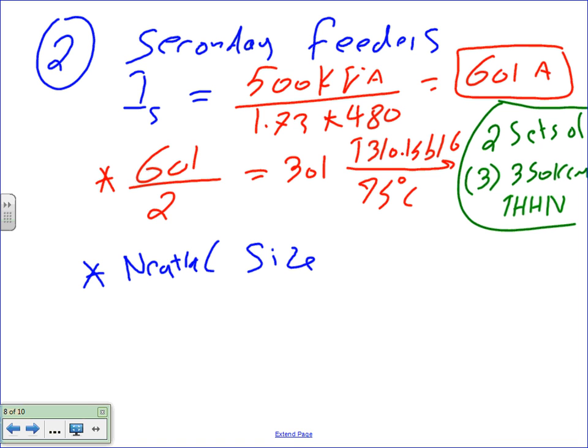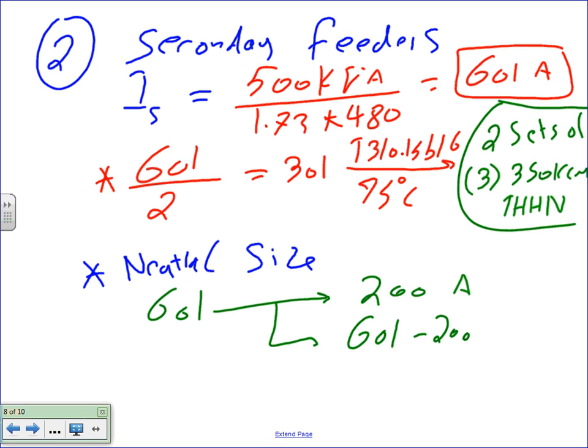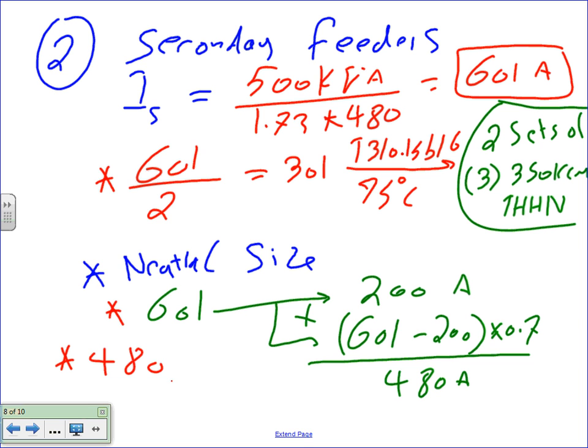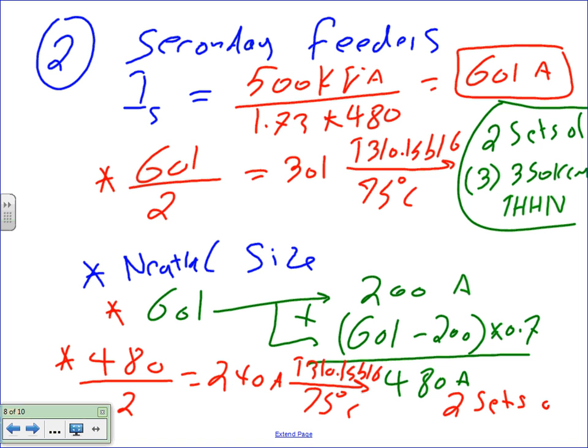An amp is, you can, so you take the 601 for the neutral, guys. The same thing, that first 200, leave them alone. Anything higher, which is 601 minus 200 times 0.7, add them up. That will get you a healthy 480 amps. And if you go down, you take the 480. Now, William, my friend, you have no chance. You have to parallel, divide by 2, give you 240 amps. You need to take this one to table 310.15(B)(16) under the 75 degree column, and that will get you the following. Two sets of one conductor, each one of them is 250 KCM THHN.